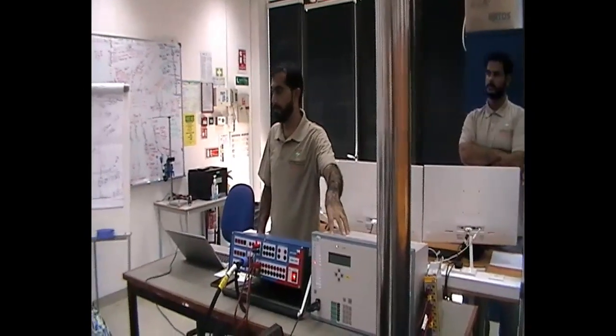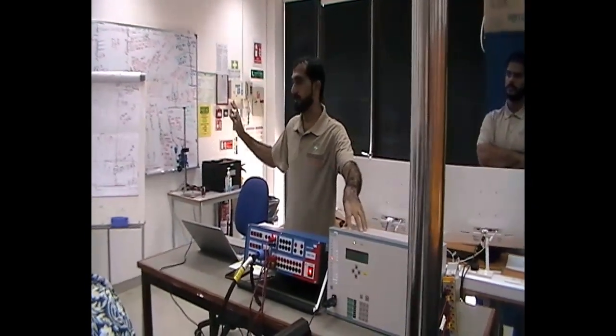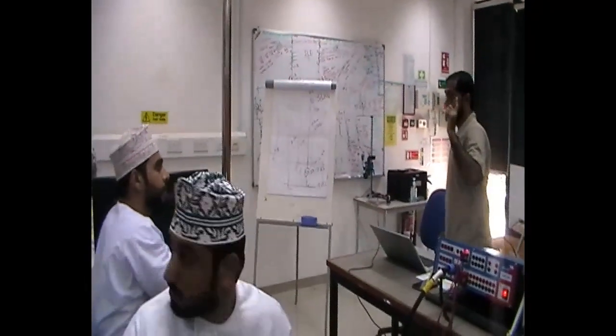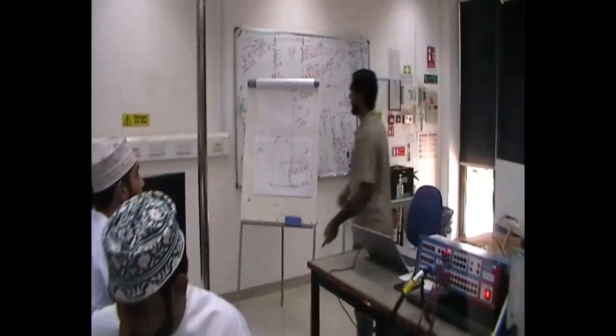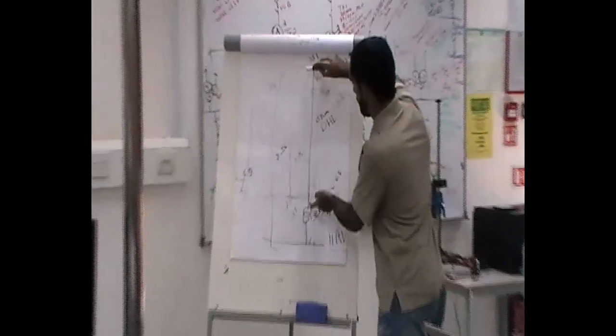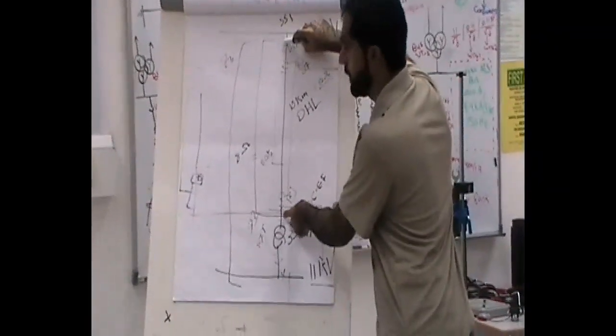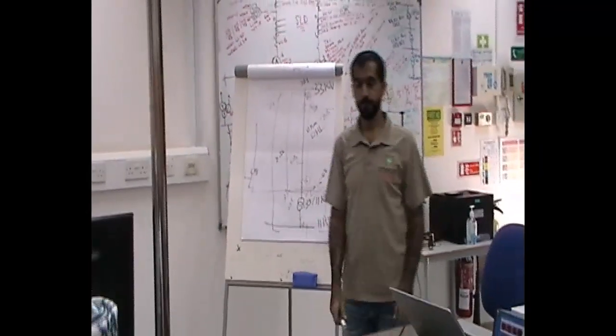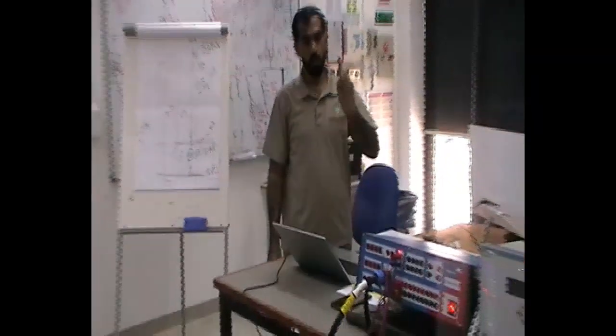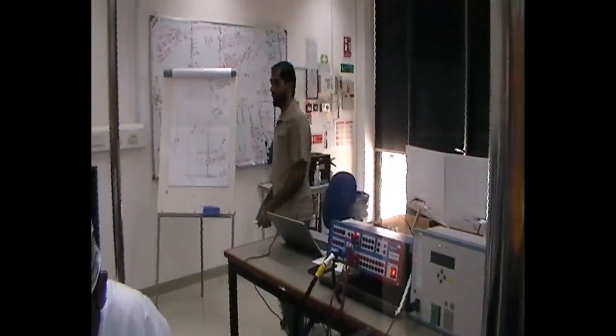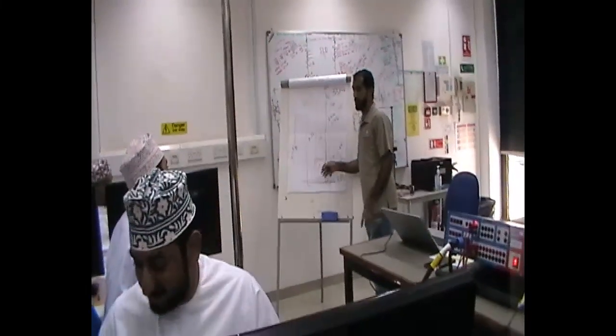If I want to use differential, I have to have... If I want differential for a line, I need communication between the sending and receiving end of the line, and I need two relays. But the distance relay is only one relay, you don't need communication. It's nothing to do here. It will not trip the breaker, will not make a reading, anything. It only takes readings from this point.